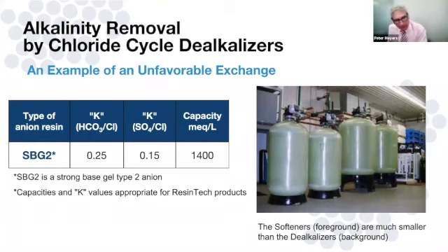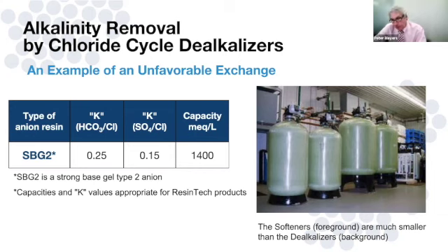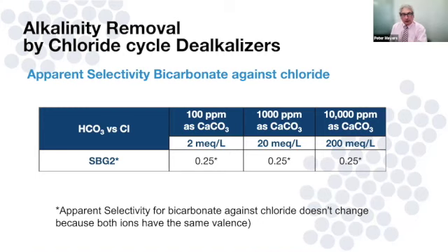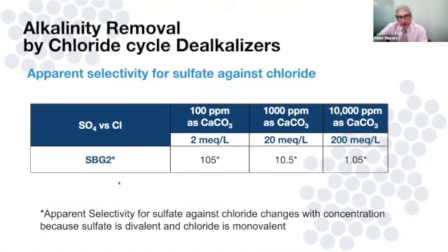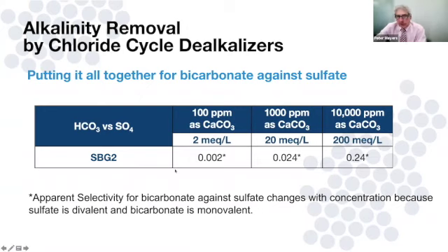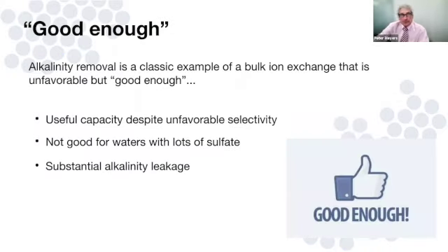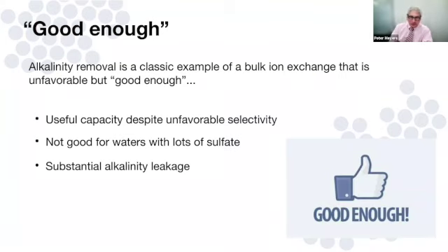Alkalinity is our last example, with unfavorable K values. The dealkalizers in this system photo are much larger than the softeners because the capacity is lower. Bicarbonate versus chloride shows no change in apparent selectivity as TDS changes, since it's a monovalent-to-monovalent exchange. Sulfate does show a big change due to its divalent-to-monovalent relationship, greatly favoring sulfate at low concentrations. Overall, this resin does not like bicarbonate compared to sulfate, but it's good enough — we get reasonable capacity, though not for waters with lots of sulfate, and there's always some alkalinity leakage.